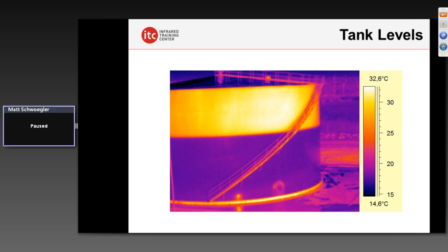For those in the petrochemical industry managing large tanks, gauges aren't always the most reliable. Infrared can actually help you locate the level inside a tank. Because of the difference in thermal capacitance between the gas and the liquid inside, we can see a level in the right conditions — of course, you need the right type of tank. Doing this on shiny stainless steel tanks is not very useful, but with a painted single-wall tank, we can easily see these levels. We can also find sludge levels in a tank — very useful data for this type of application.